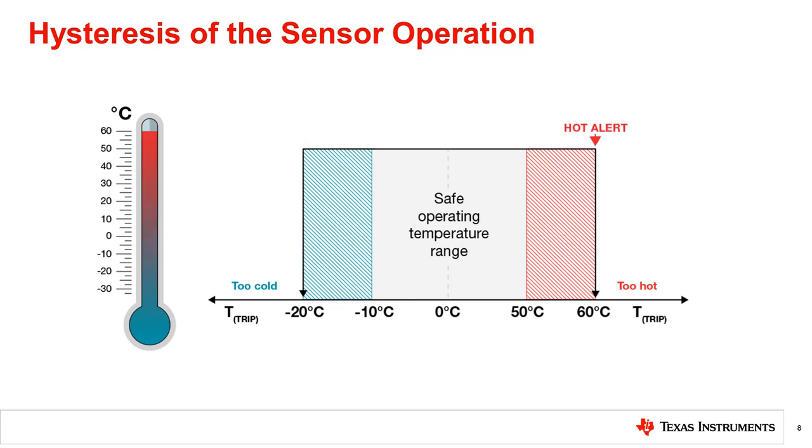Hysteresis gives your system time to settle and would ensure that your control system does not exhibit frequent power cycles. For example, in the image shown, a 10 degrees Celsius hysteresis is applied to both a warm and cold thermal limit. This would optimize your system's performance within 50 degrees Celsius to 60 degrees Celsius.